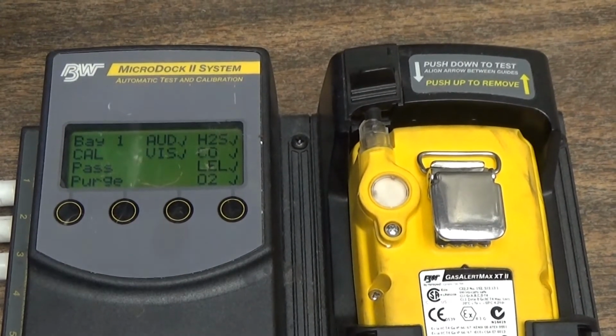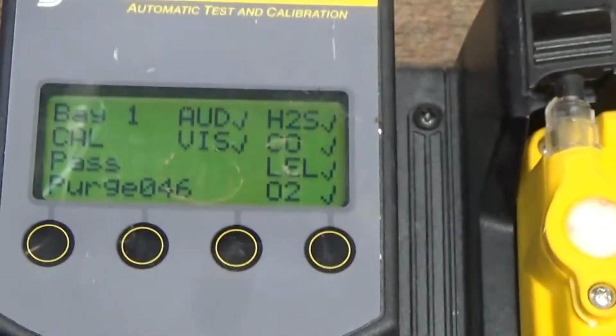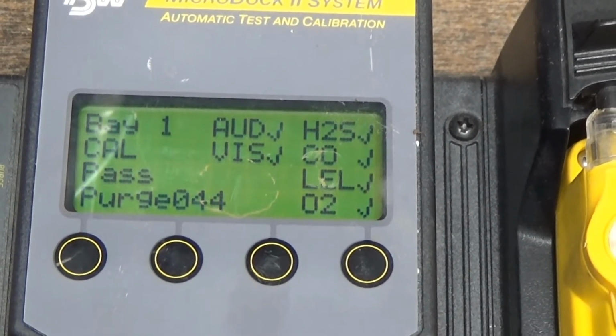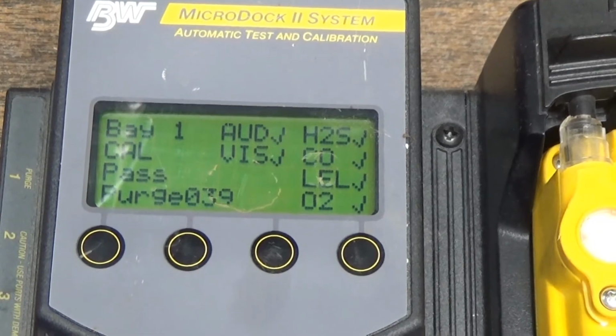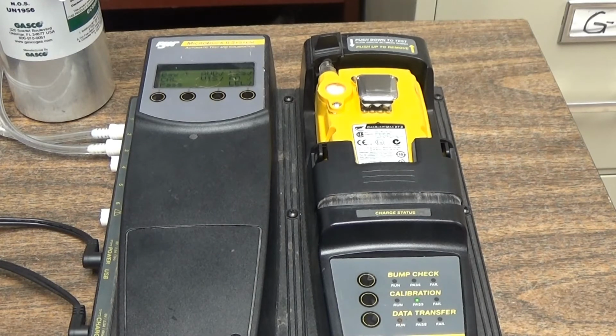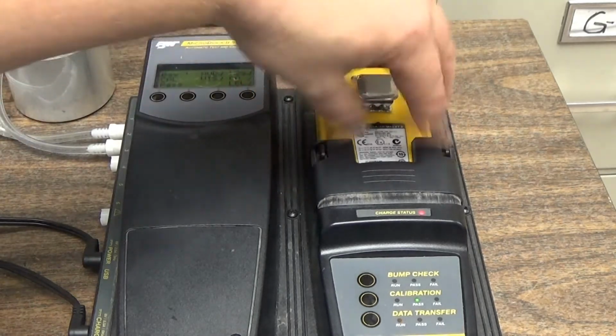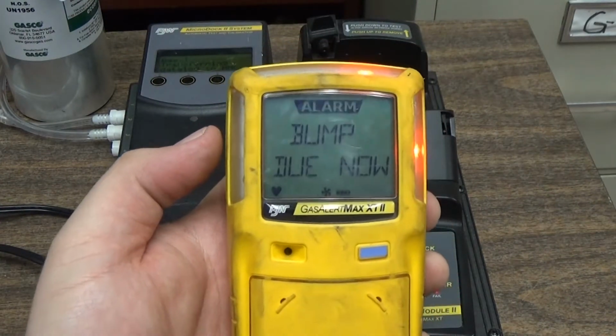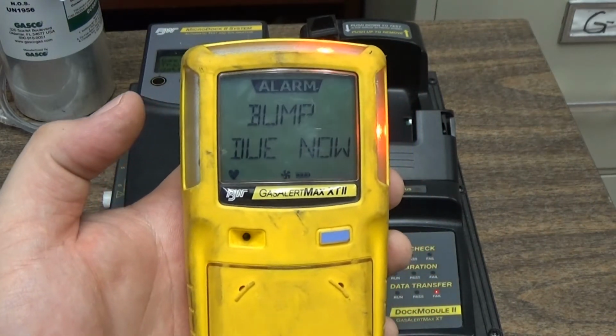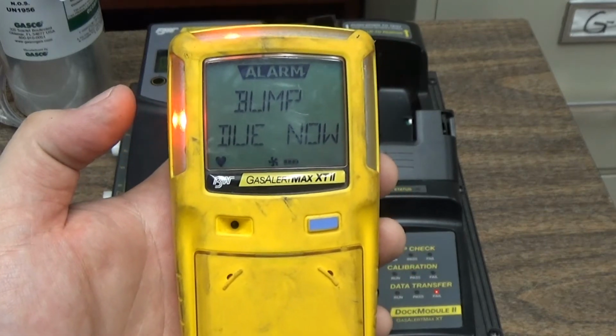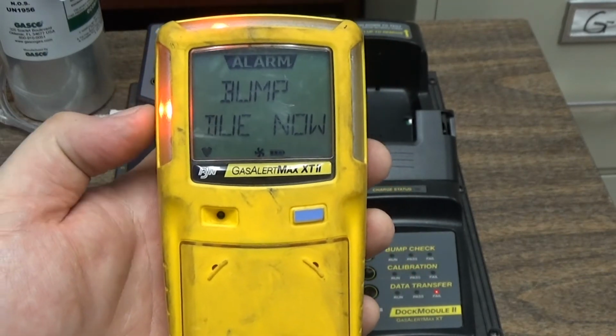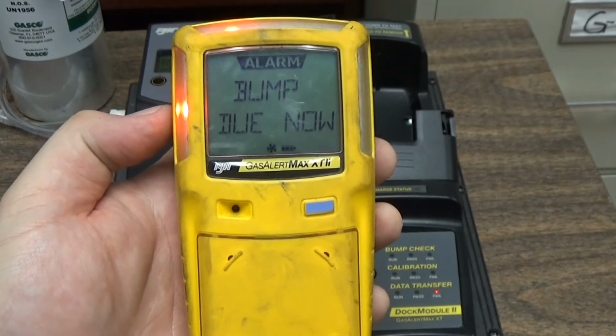After the calibration is finished, it's again going to show you if it passed or failed each sensor, and then it's going to count down the purge for 45 seconds. Let it purge until it's completely done. After it's completed the purge cycle, remove the meter from the base. The meter is then going to tell you that it must be bumped. After every calibration, you have to bump the meter for it to read all the sensors again. So be sure after the calibration to drop it right back into the bump station and run a bump check.